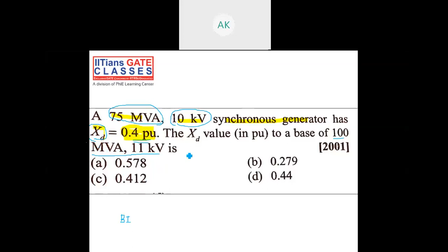Then the question they're asking is, now they have decided that there are a lot of other equipment in the system, and they want to use 100 MVA and 11 kV as their base. They are asking what will be the value of XD in this new case. Let's see how we can calculate it. There is a formula: X new is equal to X old into MVA new divided by MVA old into kV old by kV new, the whole square. If we substitute all the values that we know, we will get it as 0.44.